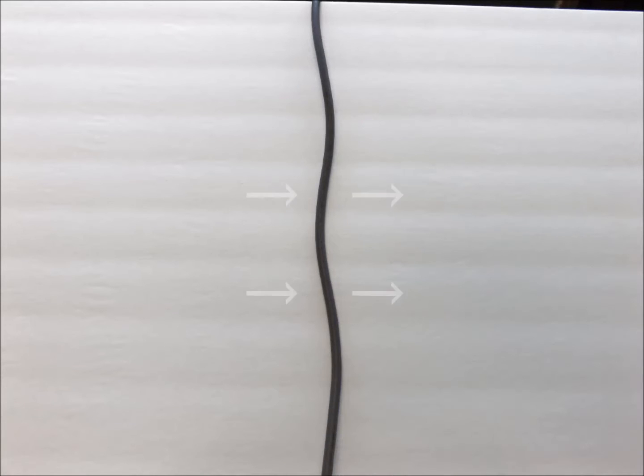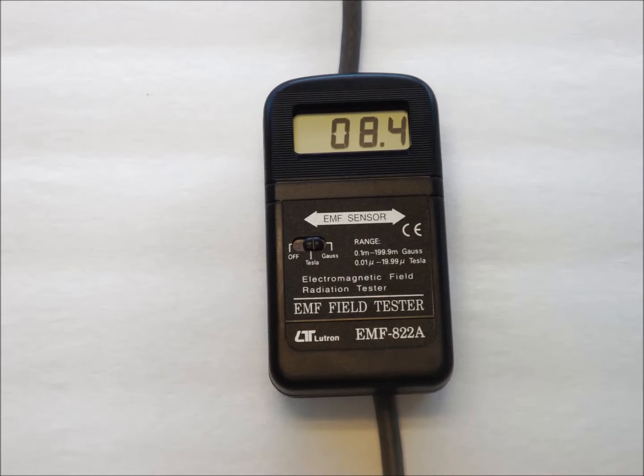In the case of this extension cord, the field is perpendicular to the cord. Holding the meter like so gives the correct reading. If the meter is turned 90 degrees from the maximum reading, it will read lower.